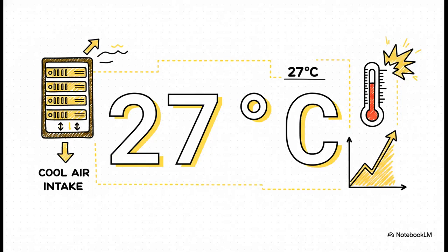And it really all comes down to one critical threshold, 27 degrees Celsius. Actually, it's more like the danger number. The energy consumption of your IT gear is directly tied to the power sucked up by the cooling fans. As the heat inside a server rack climbs, the equipment has to work overtime pulling in huge volumes of cool air just to survive. In fact, research shows that when rack temperatures push past that 27-degree mark, a server's electricity consumption can rapidly spike by up to 20%. That is a massive hit to efficiency.